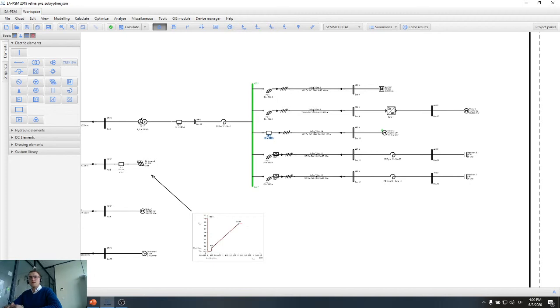How much difference between an asymmetrical fault and a symmetrical fault can damage any equipment? Basically, a symmetrical fault is only one, the three-phase short circuit current. Usually this is the biggest short circuit current, which causes not only electrical overheating damage, but also mechanical damage to the equipment, because when we have huge currents in the network, this causes mechanical forces between the equipment, and this can damage contactors. This can damage also isolators by simply breaking them.